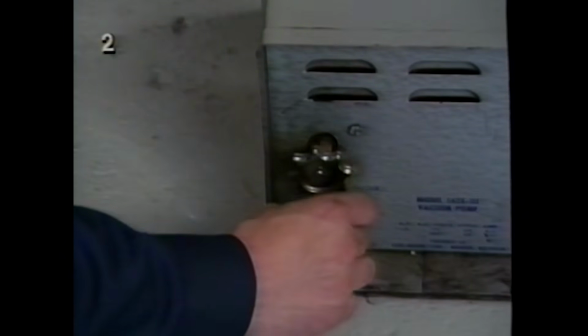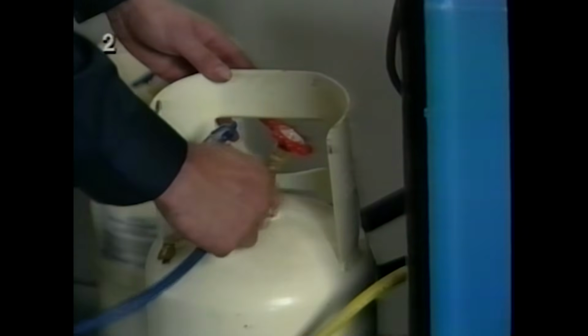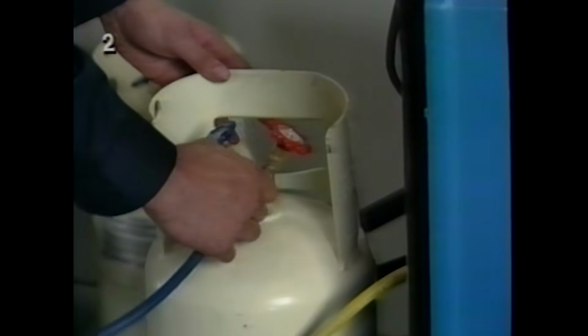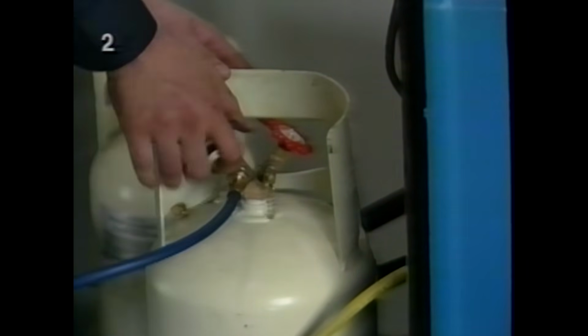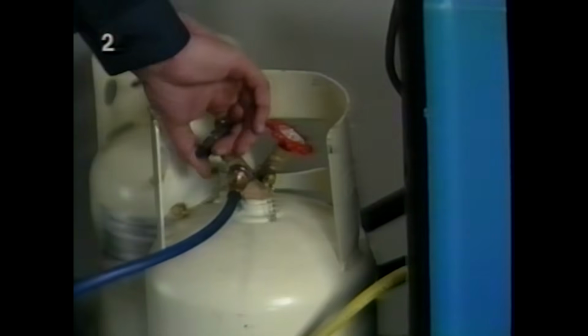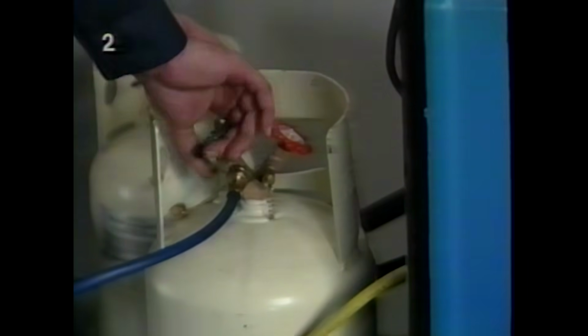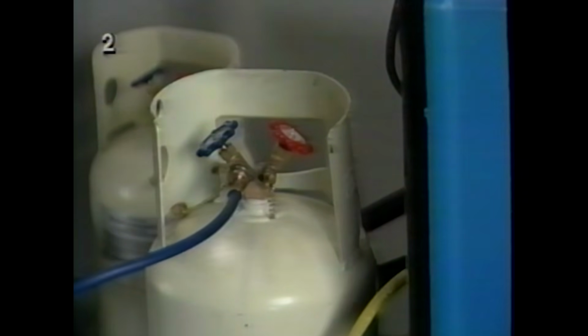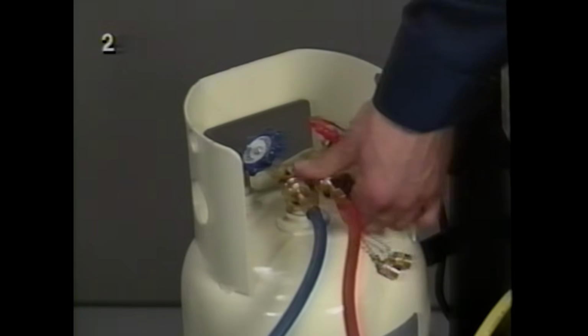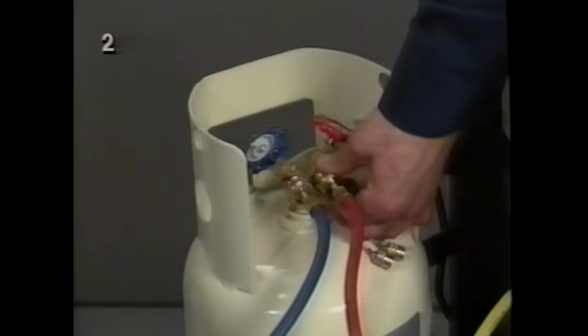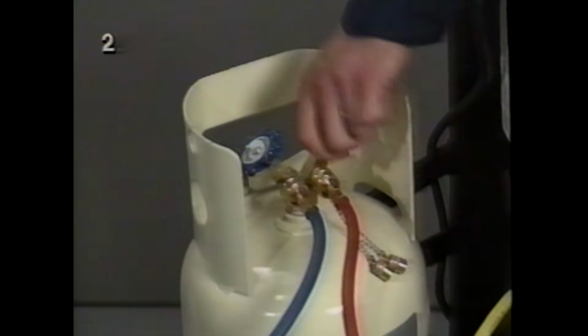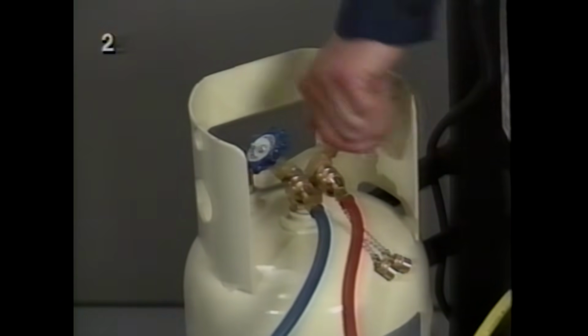Now the red hose at the rear of the station goes onto the vacuum pump. The blue hose goes to the port marked liquid on the tank. Open the liquid valve and turn the vacuum pump on. Let the system build up vacuum in the tank for about 10 minutes. Then turn off the vacuum pump and disconnect the hose from it. Then connect the red hose to the port marked vapor on the tank. Open the vapor valve and the tank is all set.